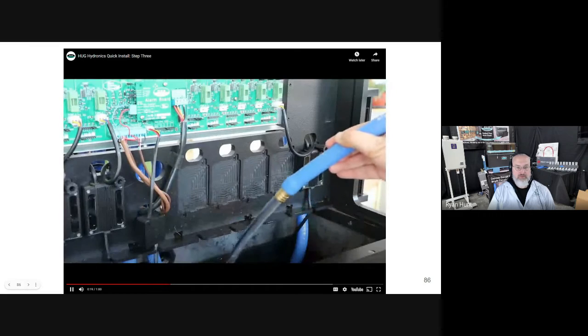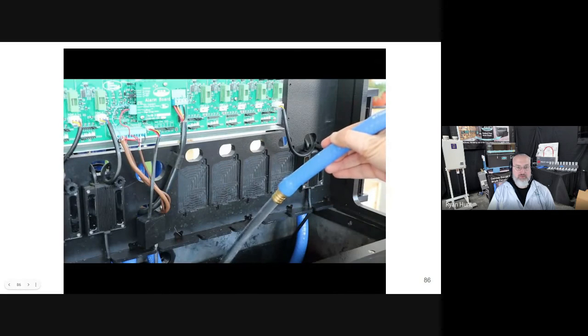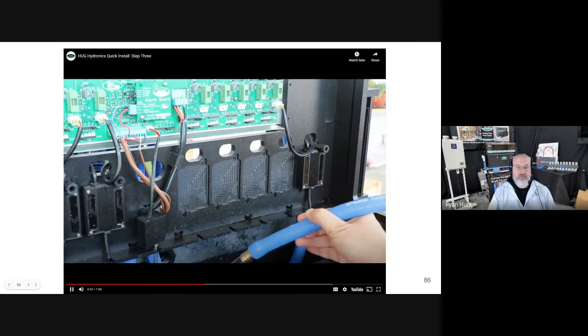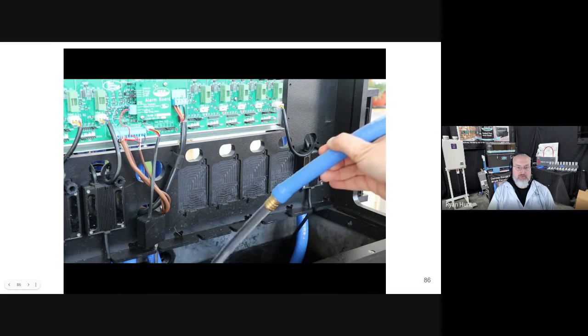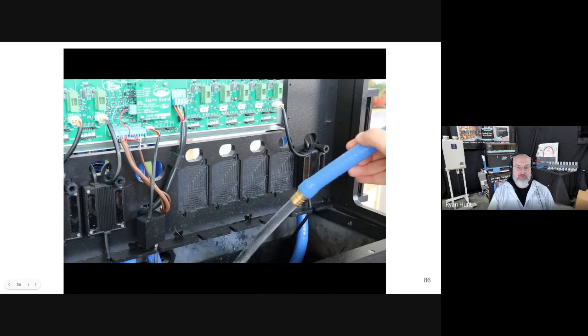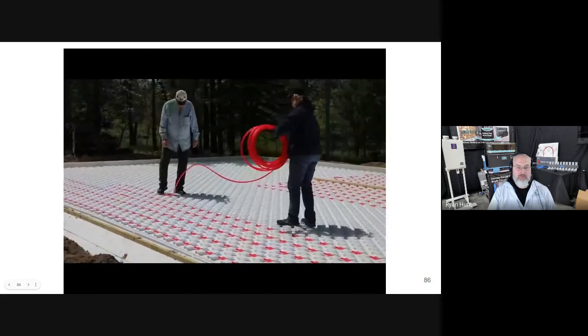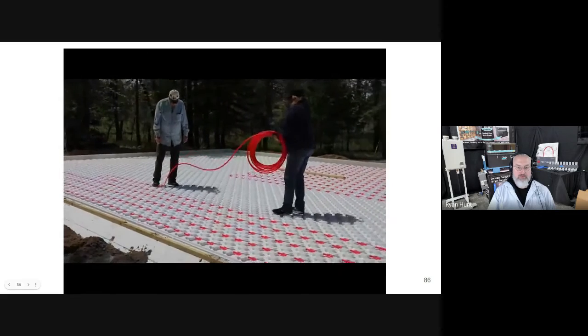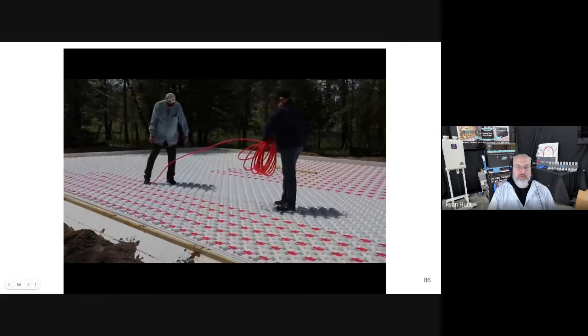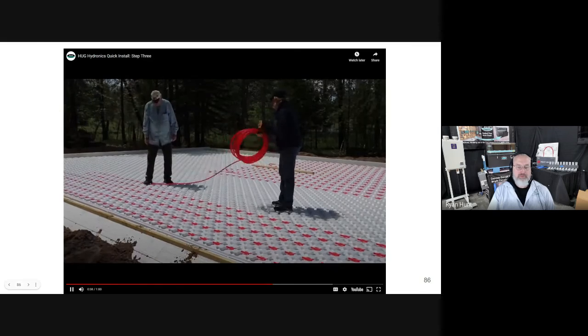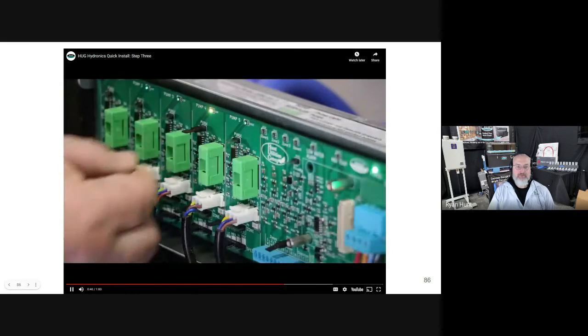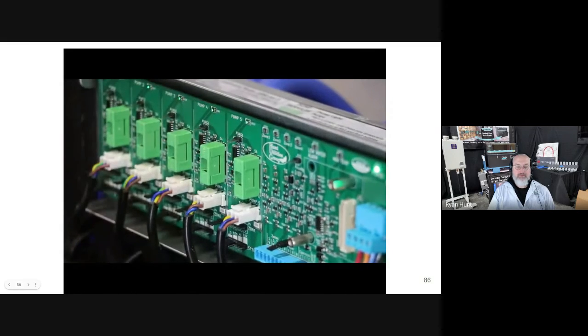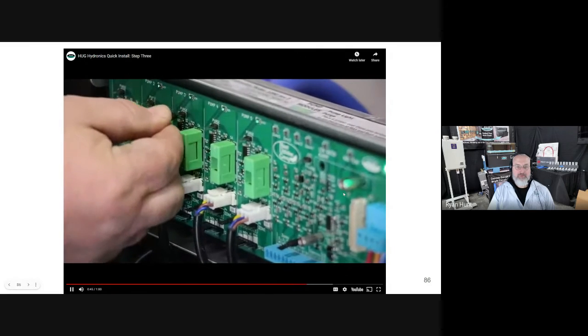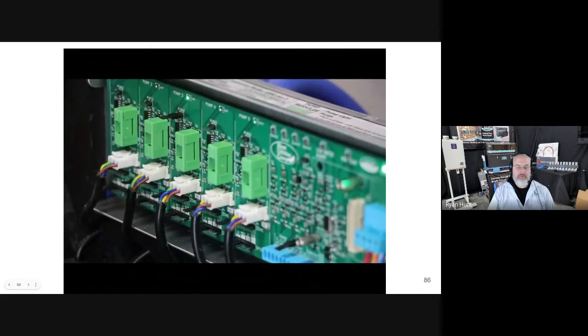Note, we recommend deionized or distilled water. Pure water is also the cheapest option and has the best heat transferability. However, you will need to note what your uses are. Each 300-foot PEX loop holds about 3 gallons of fluid. The tank holds about 8 gallons in addition to the fluid in the loops. Not all of your fluid will fit in the tank at first. You will be adding more fluid as you purge the loops.